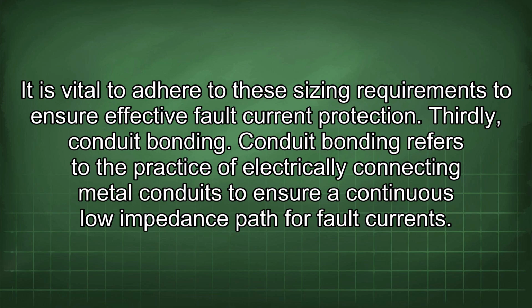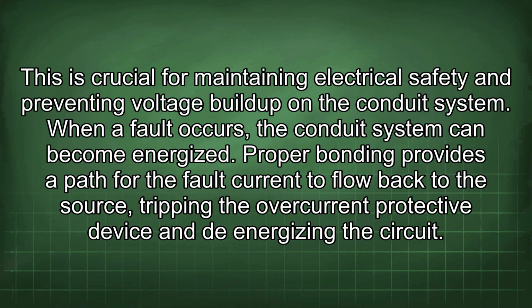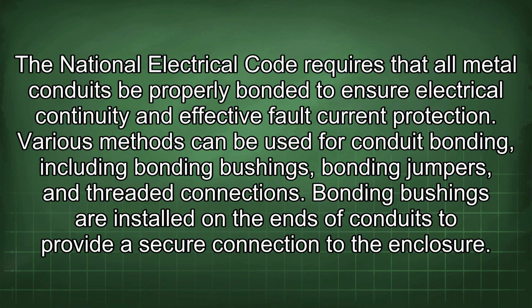Thirdly, conduit bonding. Conduit bonding refers to the practice of electrically connecting metal conduits to ensure a continuous low impedance path for fault currents. This is crucial for maintaining electrical safety and preventing voltage buildup on the conduit system. When a fault occurs, the conduit system can become energized. Proper bonding provides a path for the fault current to flow back to the source, tripping the overcurrent protective device and de-energizing the circuit. The National Electrical Code requires that all metal conduits be properly bonded to ensure electrical continuity and effective fault current protection.